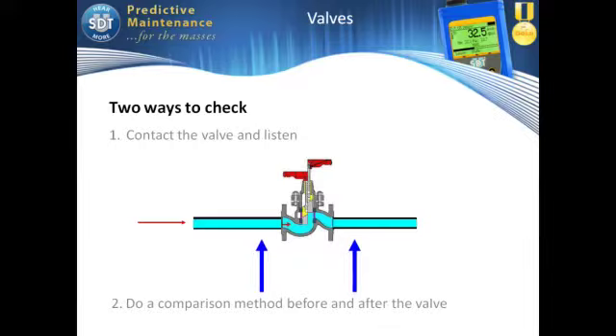A simple example, I was in a roof void in a pharmaceutical plant last year, and the valves in their steam system were all controlled by computer, and I was probably 200-300 feet away from a valve, and as soon as this valve went past 40%, it made so much noise from cavitation that 300 feet away I could still hear it ultrasonically. It was that bad. And as soon as it went back down below 40%, it stopped. It's very common. Surprisingly common.